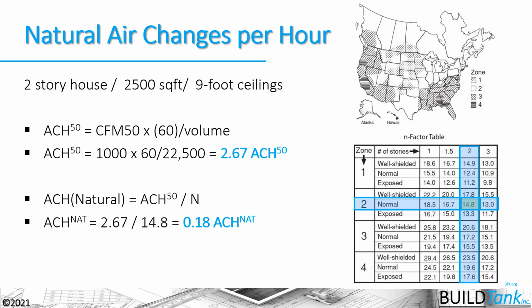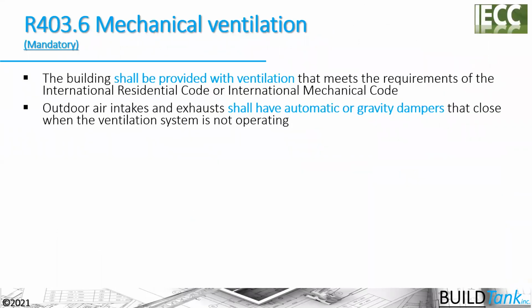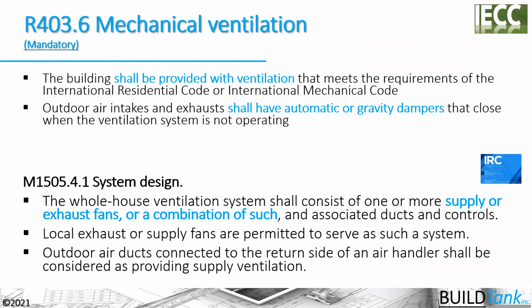Again, it depends a lot on the size of the house, but you need to make sure that you're looking at that number and have an understanding of how it equates to the actual house that you're approving there. So just to conclude that, natural air changes or the infiltration credit that you're giving to that house, we would strongly recommend that you use a blower door number versus the estimate process that Manual J allows, and that you enter it separately from mechanical ventilation, because mechanical ventilation is required by the code, and mechanical ventilation allows you to use a supply, exhaust, or balanced ventilation system that we see from the mechanical side of the code in the IRC.